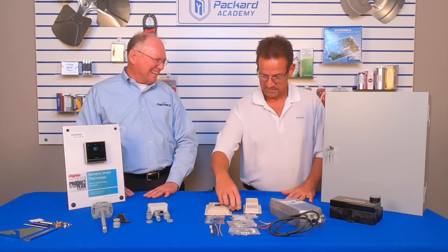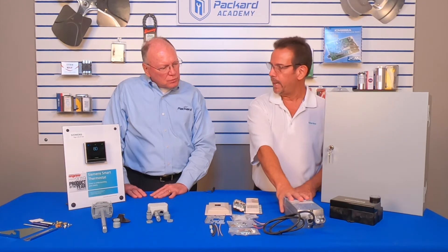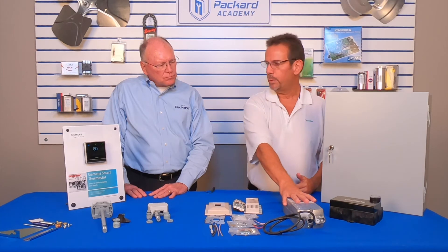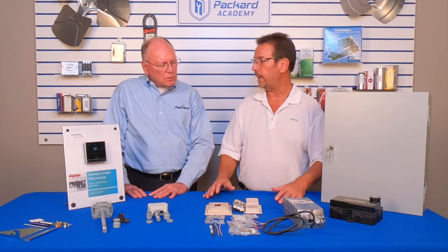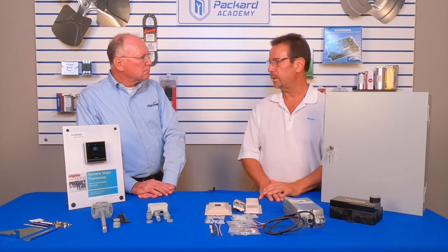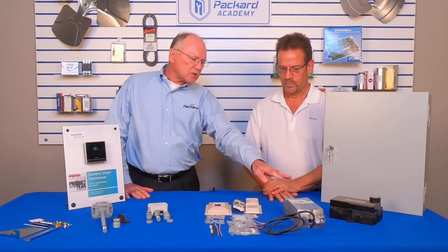This is an electrical actuator, but we also have pneumatic actuators. You have dampers to control air from one end of a building to the other, or to restrict where it's headed — we do that with pneumatics as well. We have pneumatic versions of actuators for valves depending on your environment. It could be in an explosion-proof area in an industrial application — electrical is not explosion proof, but pneumatics could be — so there are a lot of applications.